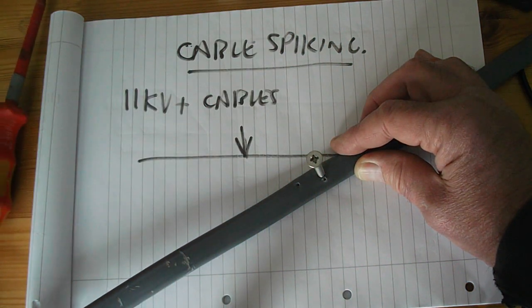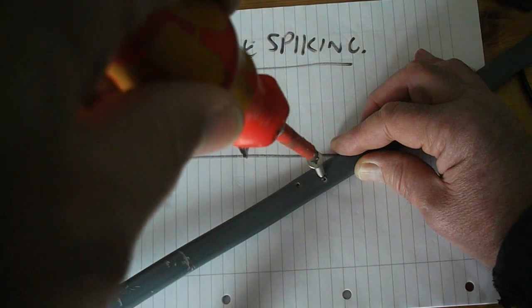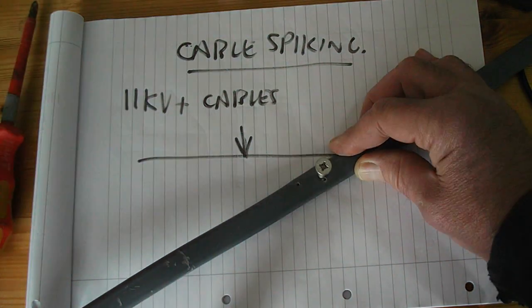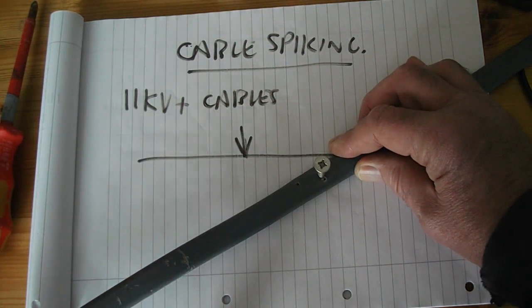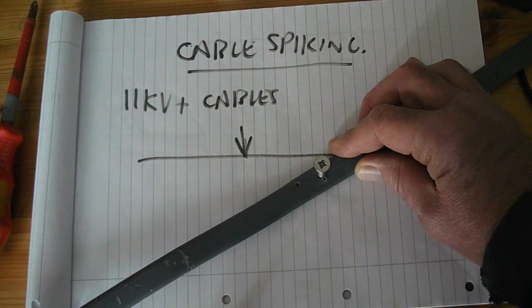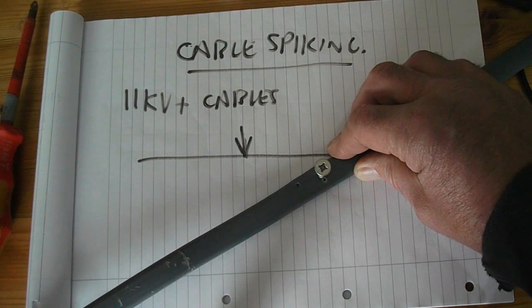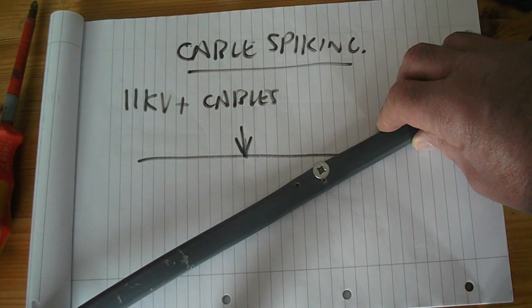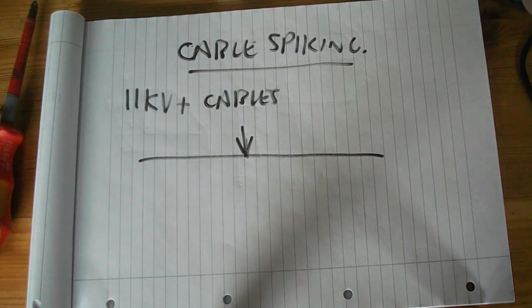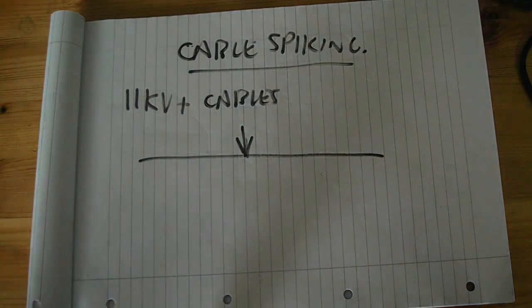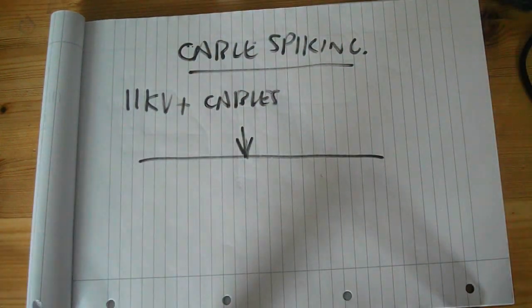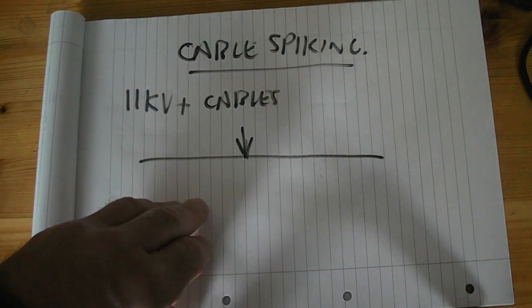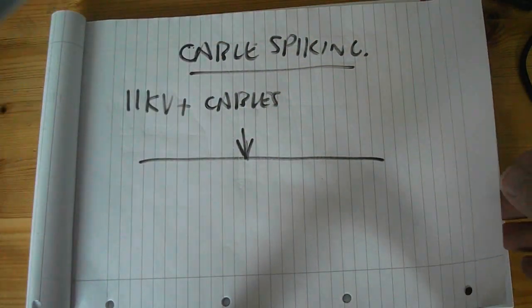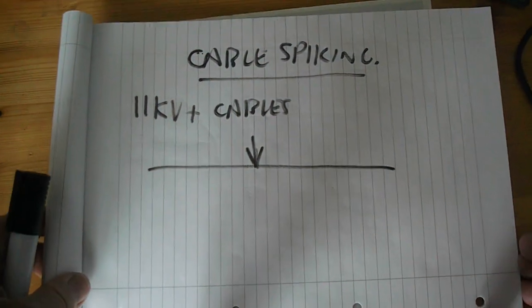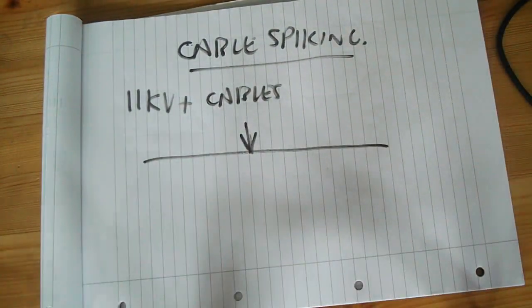But if I now disconnect the tester at one end and screw it in now, nothing happens. If the cable is live in reality, and the cable is charged to 11 kV or 33 kV, when you spike the gun there'll be an explosion, and it will cause a fuse to blow at the substation end, hopefully. Okay, so that's what cable spiking is about. It proves that the cable is dead, because it has to be disconnected first. Okay, right.